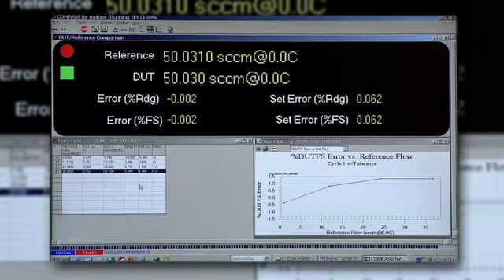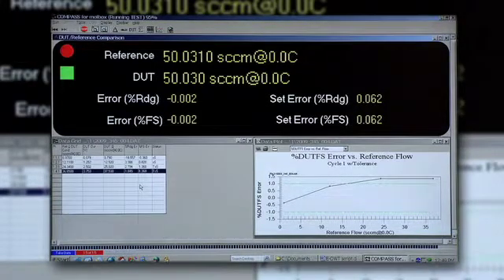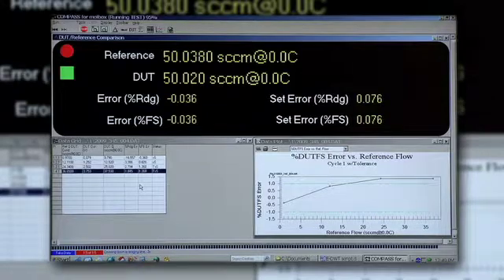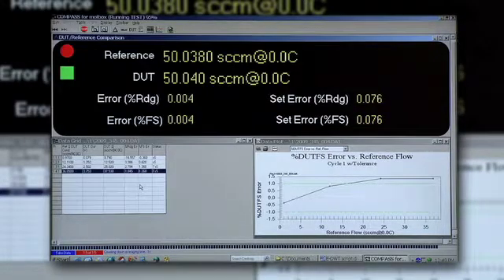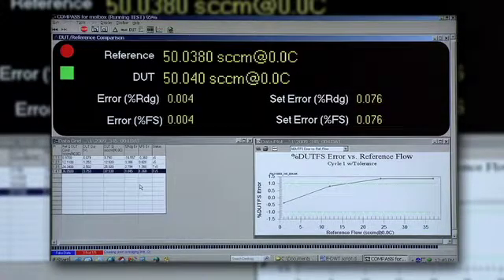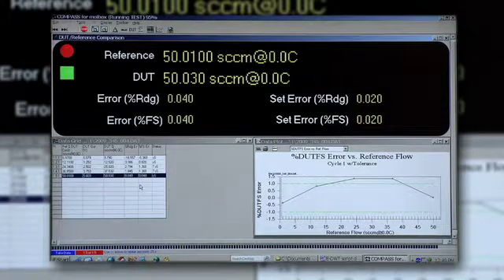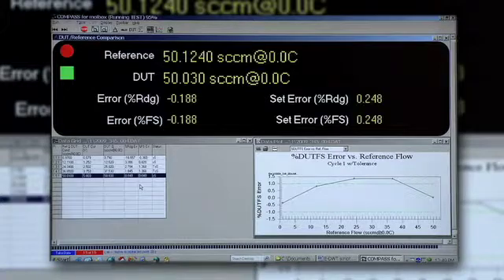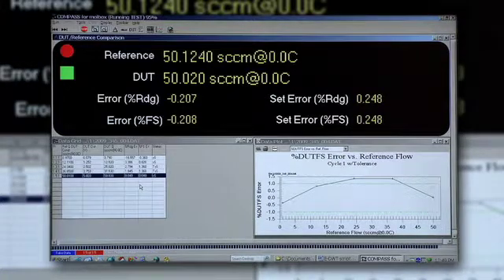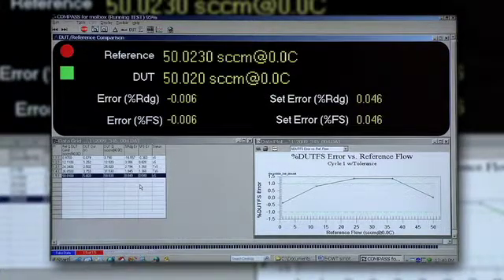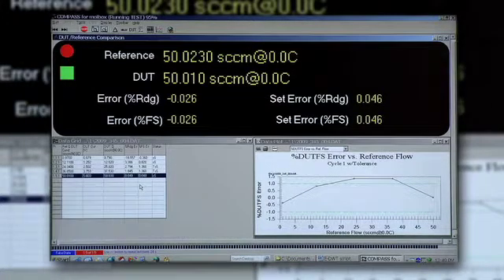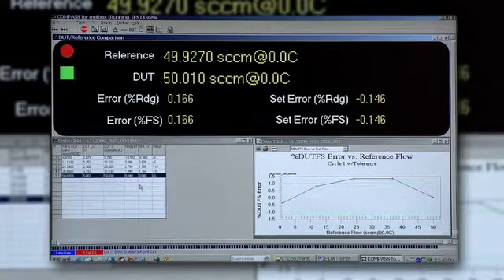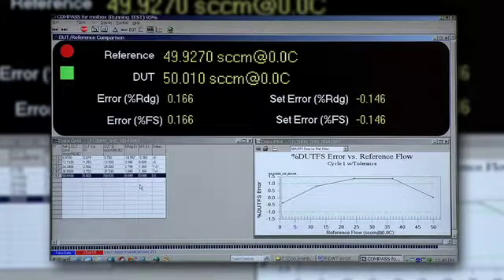Right now we have a good looking data point at 50 SCCM, or 100 percent of the range of the MFC. And there's our final point recorded which shows in tolerance at the top and bottom but a pretty poor linearity and some need for adjustment particularly in the middle of the range.